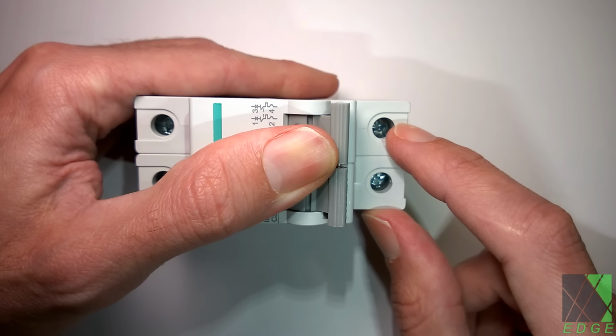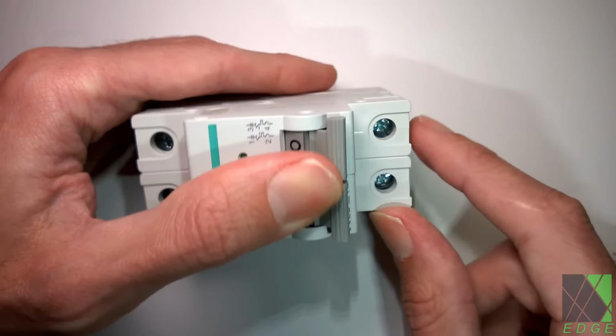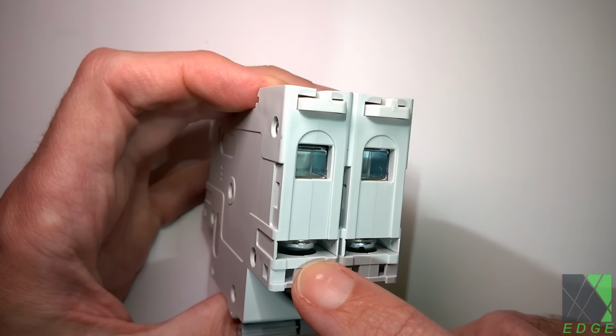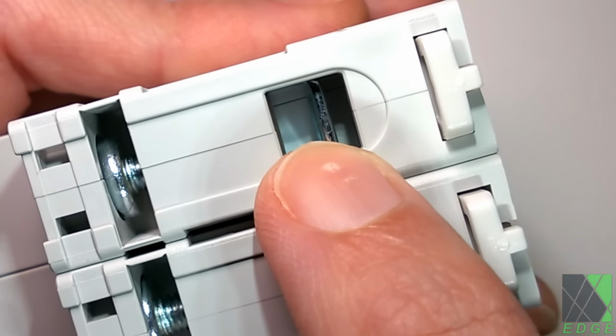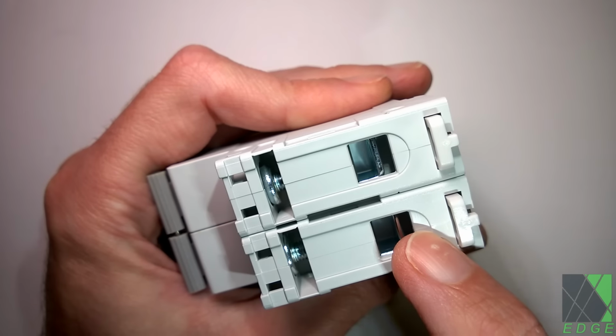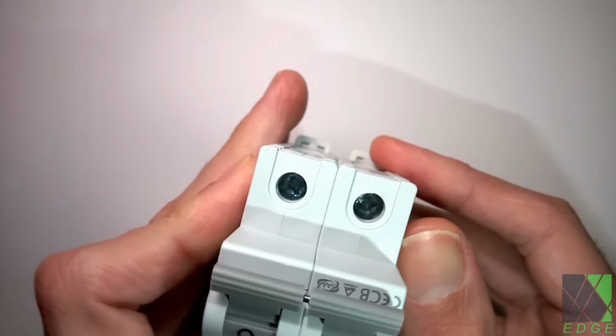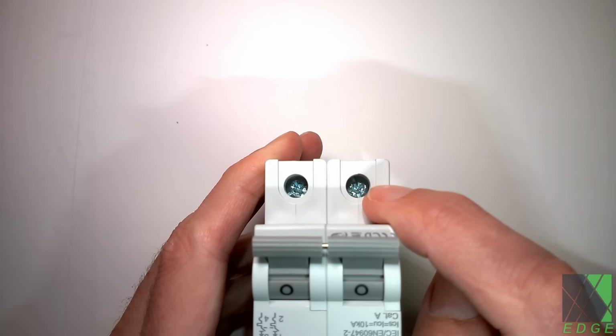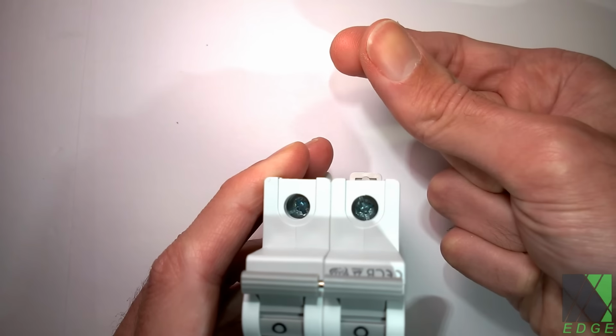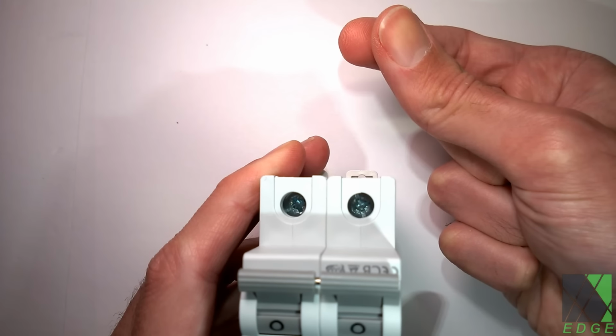When installing a circuit breaker, make sure and torque the terminals properly. Thermal expansion and contraction makes the wires want to move. The breaker will naturally warm up and cool down over the course of normal use. This can cause loose wires, which can lead to arcing, heat, and fire. Wires should also be clamped down near the breaker so they don't move at all.